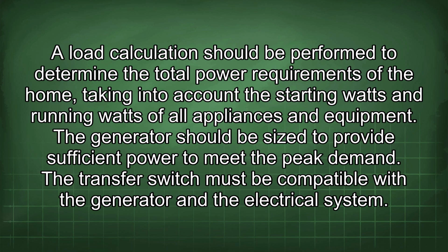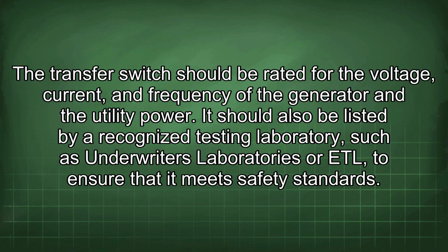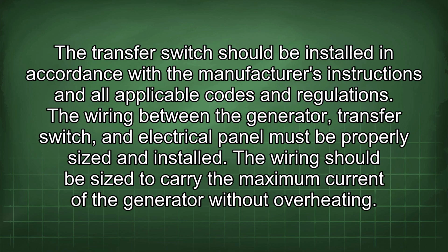The transfer switch must be compatible with the generator and the electrical system. The transfer switch should be rated for the voltage, current, and frequency of the generator and the utility power. It should also be listed by a recognized testing laboratory, such as Underwriters Laboratories or ETL, to ensure that it meets safety standards. The transfer switch should be installed in accordance with the manufacturer's instructions and all applicable codes and regulations.